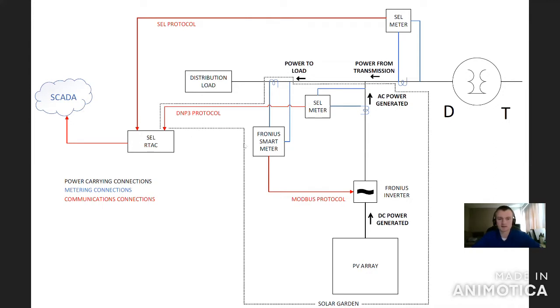What we'd be adding is shown in the dashed box: a solar garden consisting of a PV array, which generates DC power that gets converted to AC through an inverter and injected directly onto the distribution grid. There'd also be a similar SEL power meter to what already exists, tracking how much power is being injected from the solar garden, and sending that information to the real-time automation controller for the municipality's own reporting purposes.